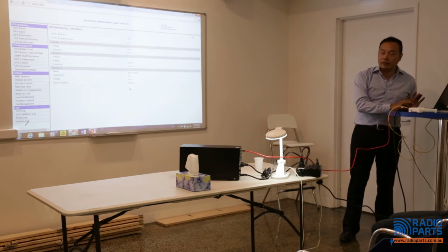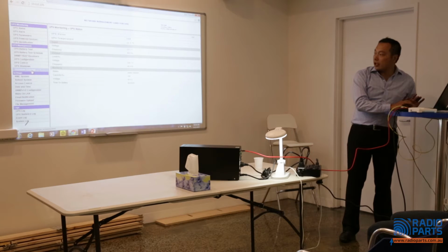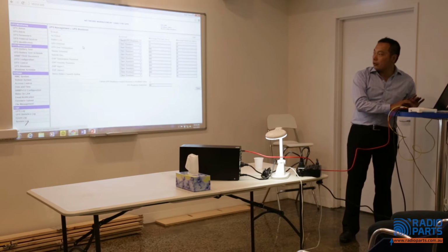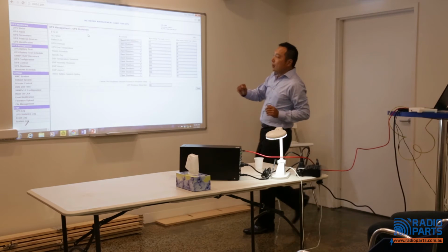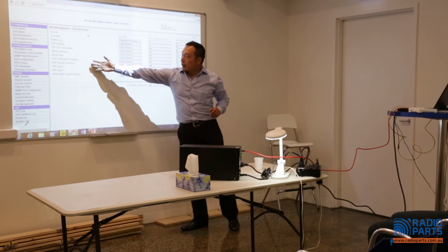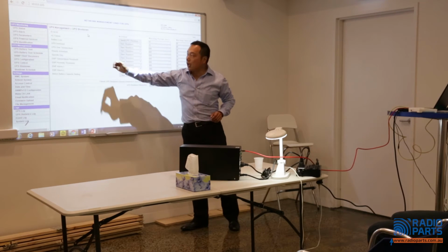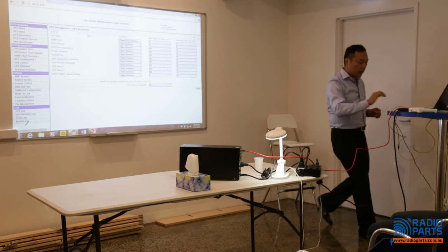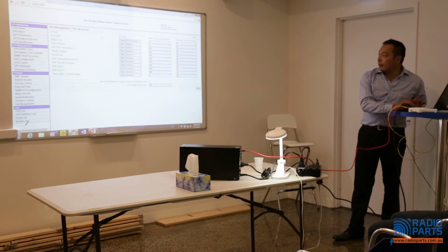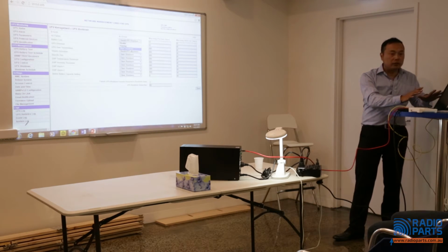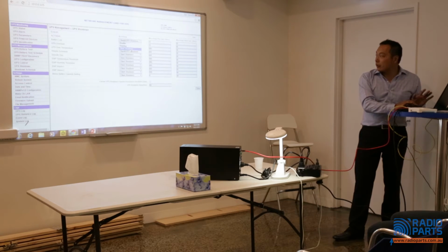Now the shutdown function here, I'm going to show you. UPS has a lot of events. When AC fails, when the battery is low, you can set this action warning interval. When AC fails, you can disable, send a warning, client shutdown which means you only shut down the server or PC, or shut down both client and UPS. Then warning period 10 seconds, you can change it here.